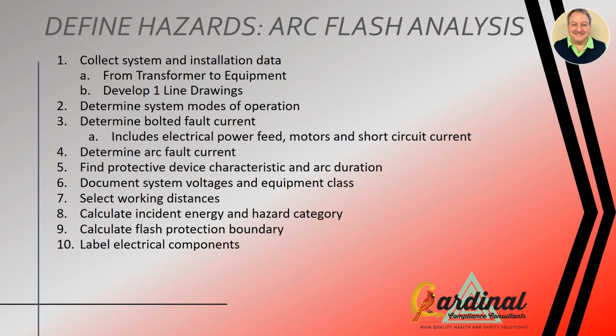And that is a combined study looking at your incoming power feed, your equipment, and also in-house, the size of your motors, the type of the motors, and your neighbors also have some effect on you, in that if they have a large number of big motors, over 50 horsepower, there will be some added boost to the short circuit current in that area that is in addition to what the generators of the power company can put out. So the electrical systems are rather complex and need to be looked at properly to understand what that is.